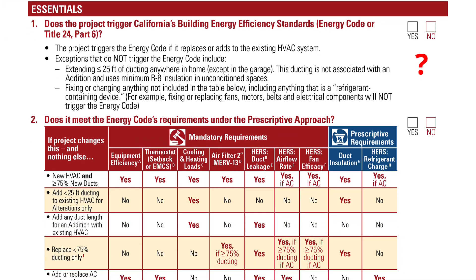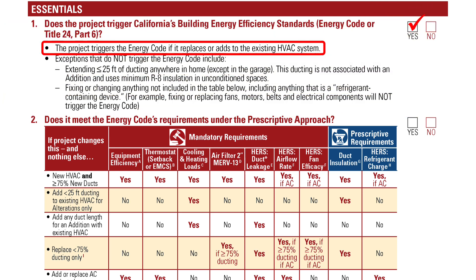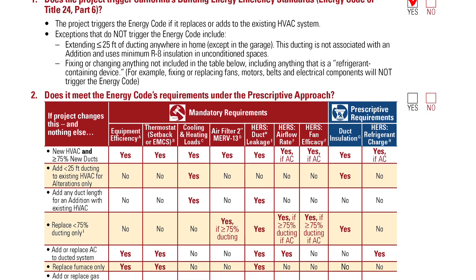Given what's shown, would this type of project trigger the energy code? Yes, according to the checklist, a total HVAC replacement would trigger the energy code. Replacing part of an HVAC system would as well. Extensive home renovations where the building department requires building design plans would also be supported in this checklist.